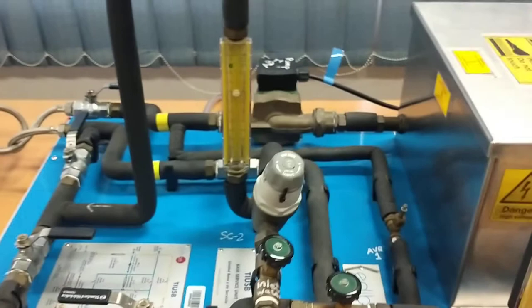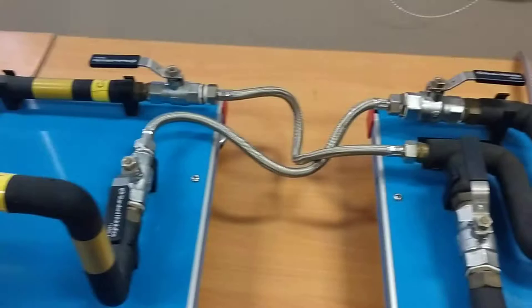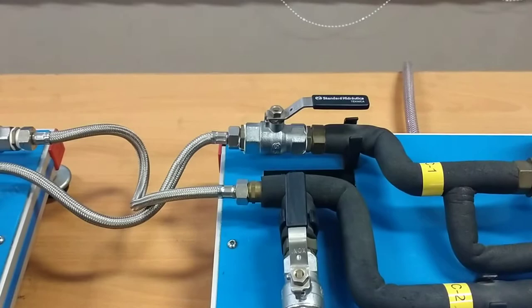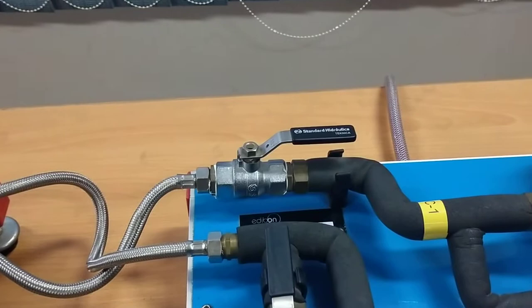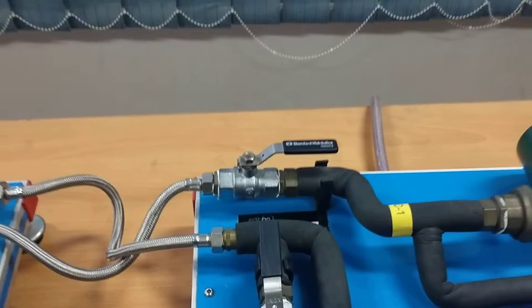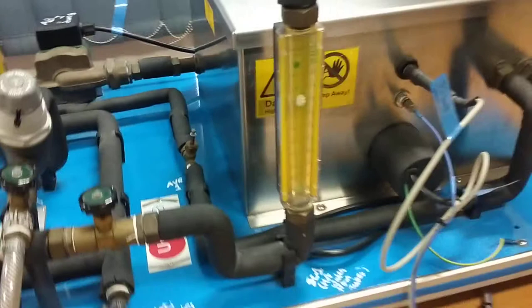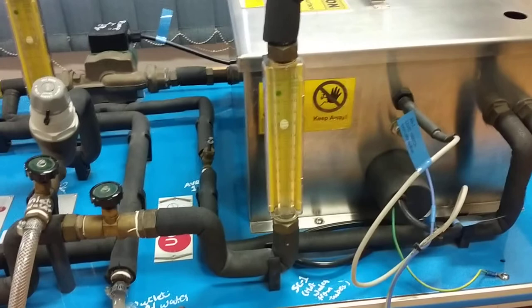So you can now trace the path of the hot water. You can see that this one is the exit of the hot water. The pump will supply energy to the water, and from the pipe it will move to C1. This valve must be open. If I close this valve, there will be no flow of the hot water, and I can deduce that there is no flow in the hot water channel from this flow meter. So there should be a reading on the flow meter showing that there's flow of the hot water.